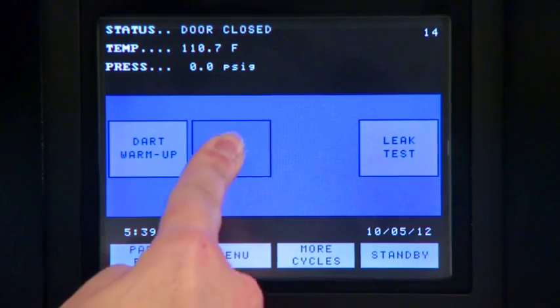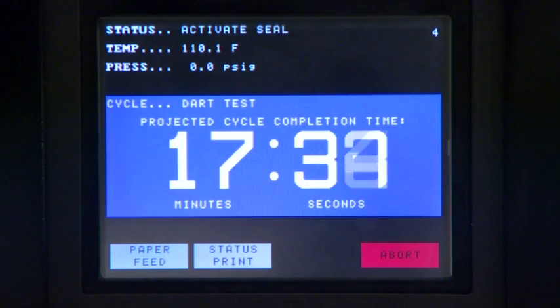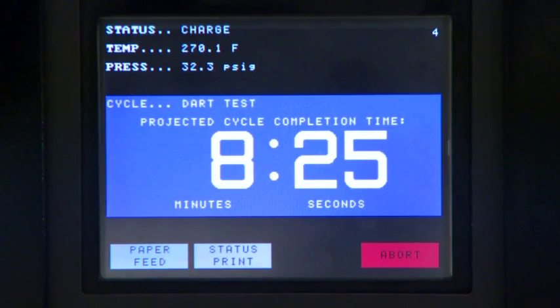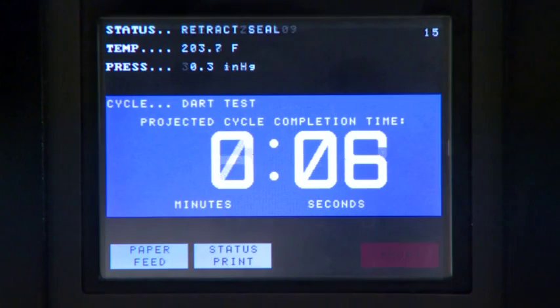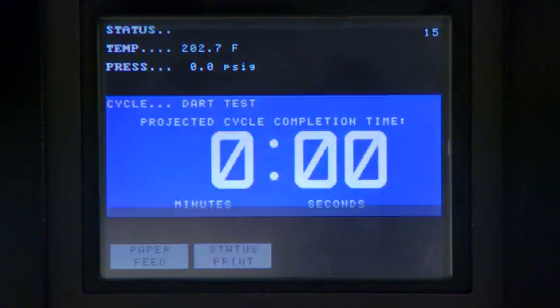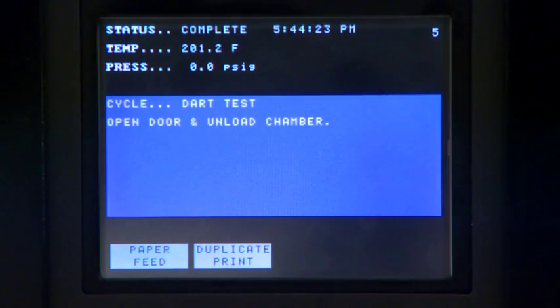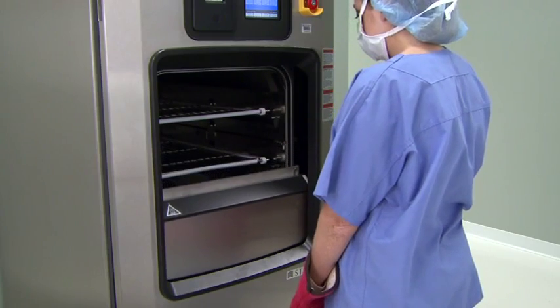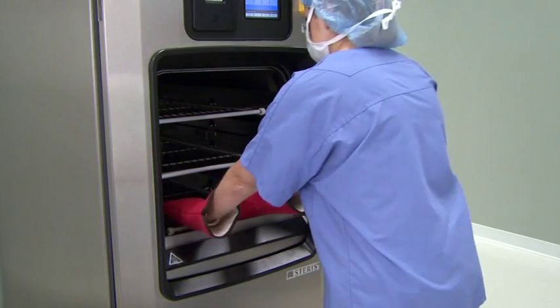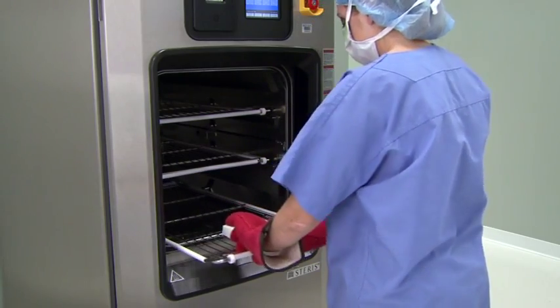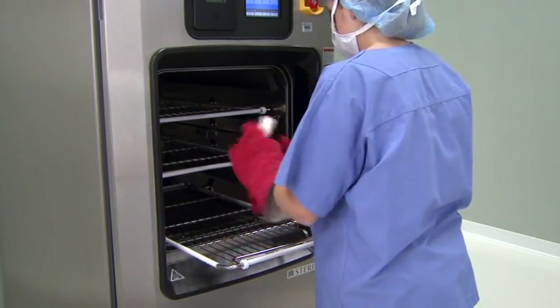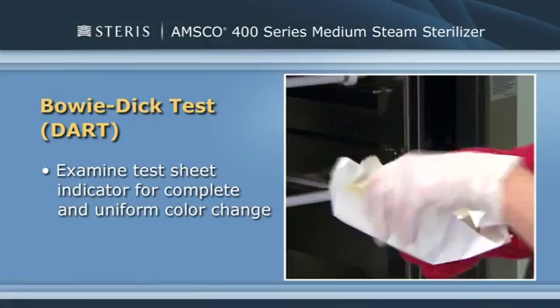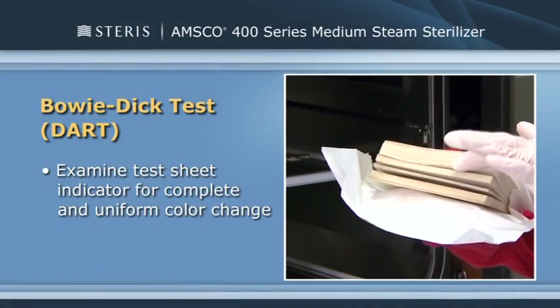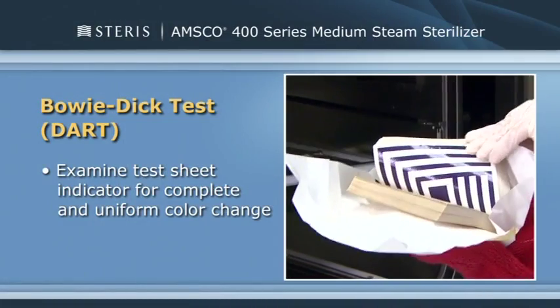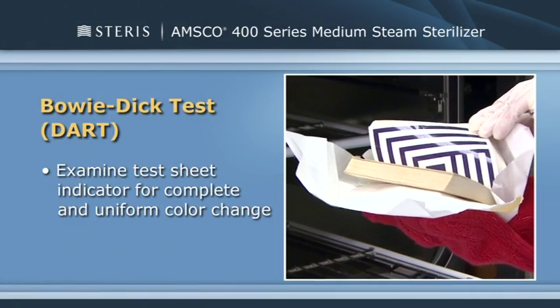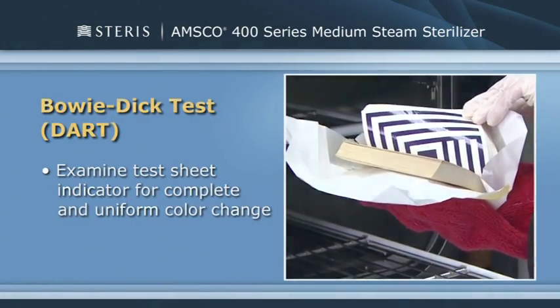Press the DART test button to begin the cycle. The sterilizer temperature will reach 270 degrees Fahrenheit. After 3.5 minutes of sterilize time and 1 minute of dry time, the test cycle is complete. Open the chamber door at the conclusion of the cycle and, wearing your personal protective equipment, carefully remove and open the DART test or Bowie-Dick test pack. Examine the test sheet indicator for complete and uniform color change. The entire cycle is also documented on the test cycle printout.